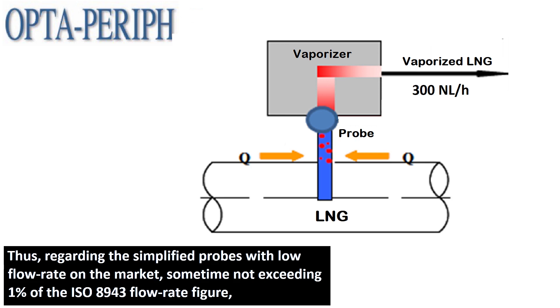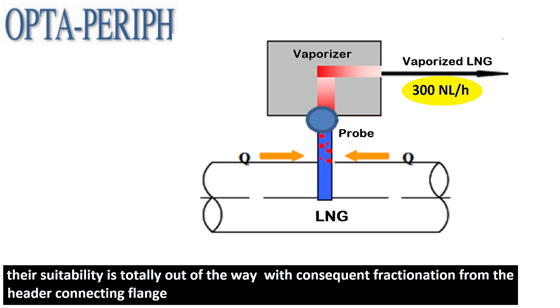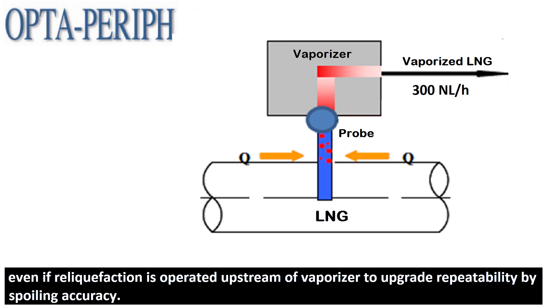Thus, regarding the simplified probes with low flow rate on the market, sometimes not exceeding 1% of the ISO 8943 flow rate figure, their suitability is totally out of compliance, with consequent fractionation from the header connecting flange, even if reliquefaction is operated upstream of the vaporizer to upgrade repeatability by spoiling accuracy.